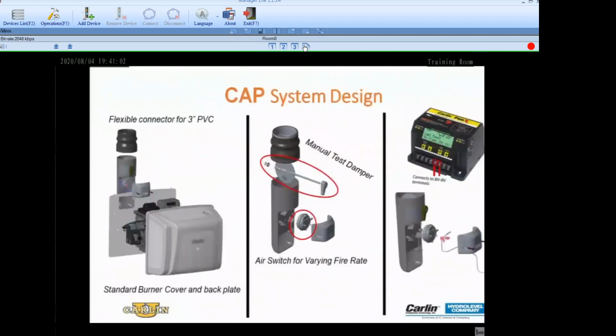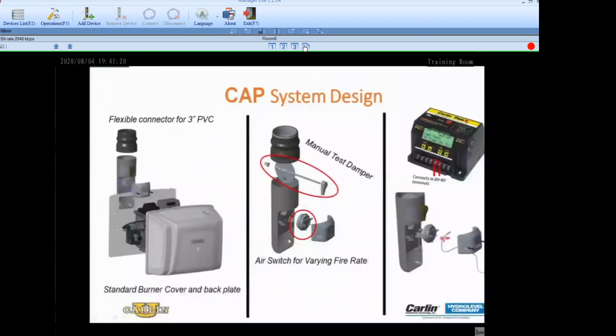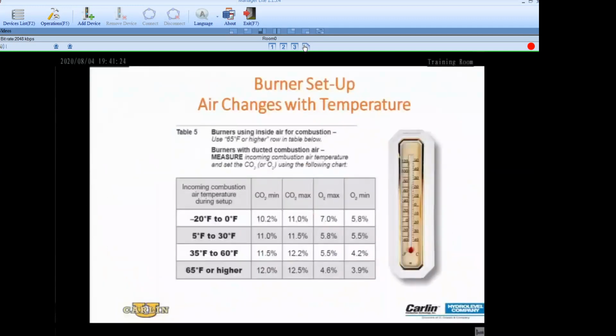So there's a connector for 3-inch PVC or galvanized pipe. There is a test damper built in. There's a switch located right here in the snorkel, and that switch is connected to the primary control, allowing you to sense a blockage in combustion air.